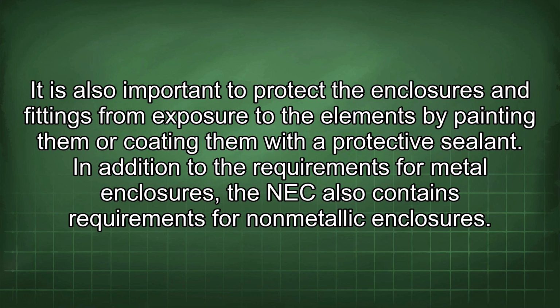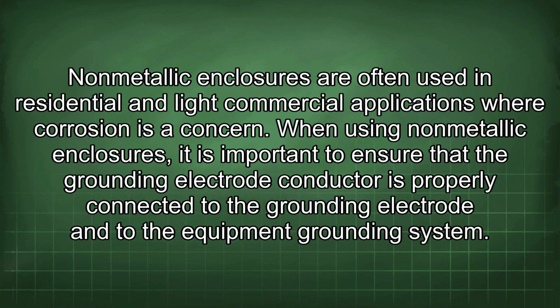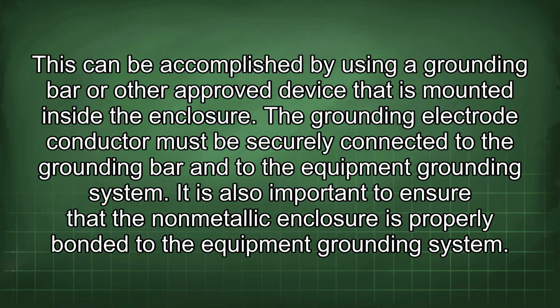In addition to the requirements for metal enclosures, the NEC also contains requirements for non-metallic enclosures. Non-metallic enclosures are often used in residential and light commercial applications where corrosion is a concern. When using non-metallic enclosures, it is important to ensure that the grounding electrode conductor is properly connected to the grounding electrode and to the equipment grounding system. This can be accomplished by using a grounding bar or other approved device that is mounted inside the enclosure. The grounding electrode conductor must be securely connected to the grounding bar and to the equipment grounding system.